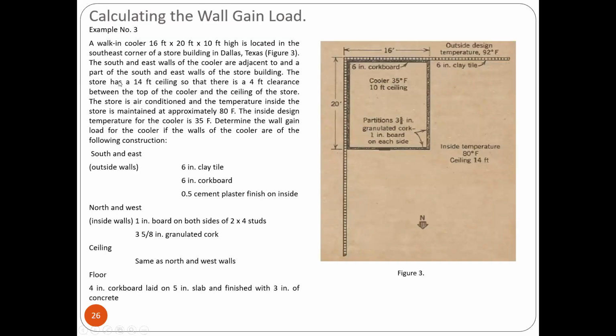So example number 3. A walk-in cooler 16 feet by 20 feet by 10 feet high is located in southeast corner of a store building in Dallas, Texas. Figure this, southeast. Di ba? So sabihin natin na sa southeast siya. Corner. The south and east wall of the cooler are adjacent to a part of the south and east wall of the store building. The store has a 14-feet ceiling so that there is a 4-feet clearance between the top of the cooler and the ceiling of the store. Okay. The store is air conditioned and the temperature inside the store is maintained at approximately 80 Fahrenheit. So the inside design temperature for the cooler is 35. Determine the wall gain load for the cooler if the walls of the cooler are of the following construction.